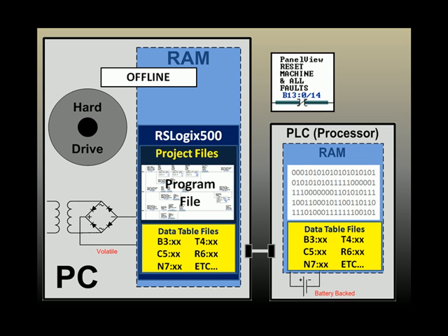0/14. That tag name or variable is examined by a true if off instruction at that memory location in the copy of the data table files located in RAM in your personal computer, which is in the offline state. When it reads that address, it sees that address is off, and because it's a true if off instruction, then the instruction is true. Therefore, it is highlighted or true. That information, though, comes from the data table files that are on your personal computer.